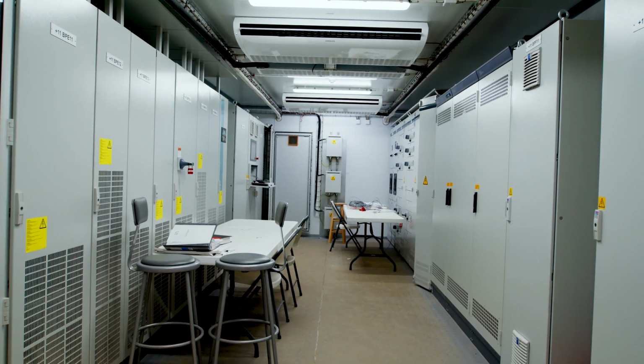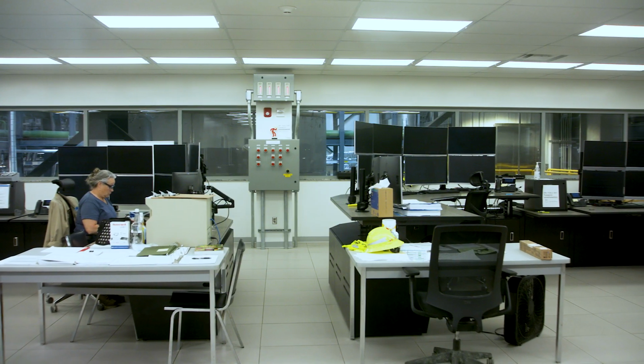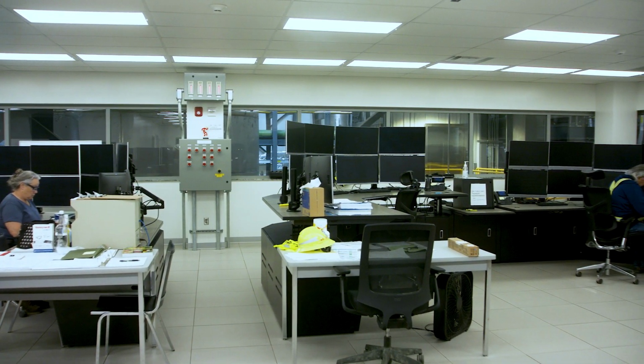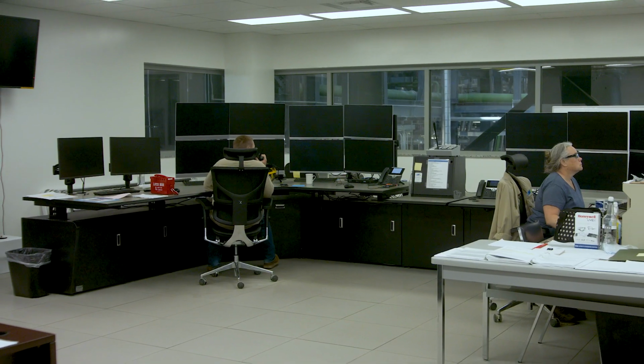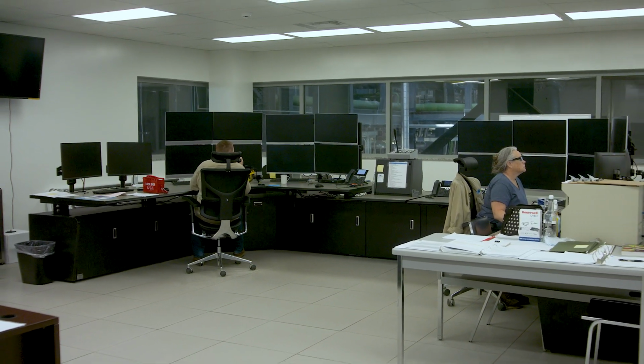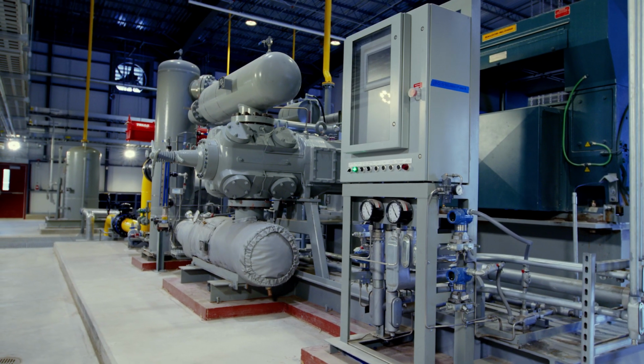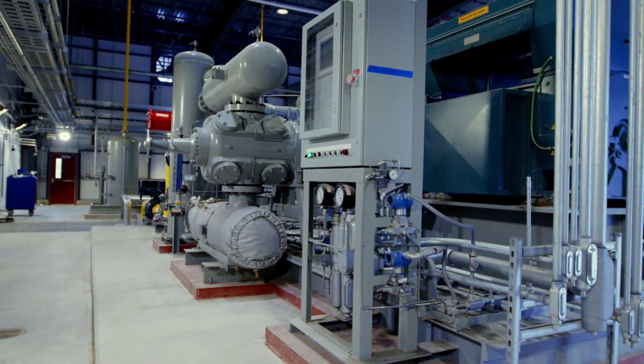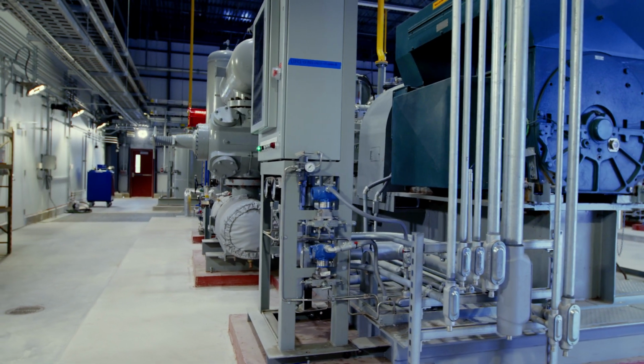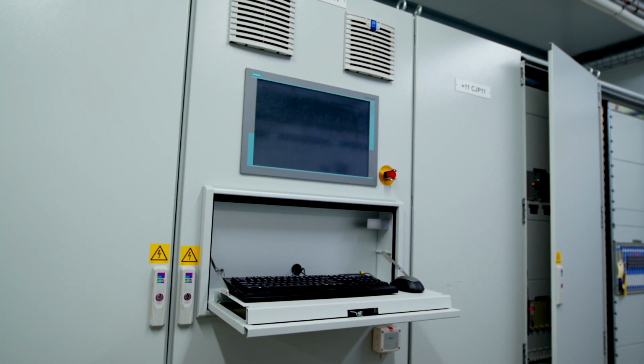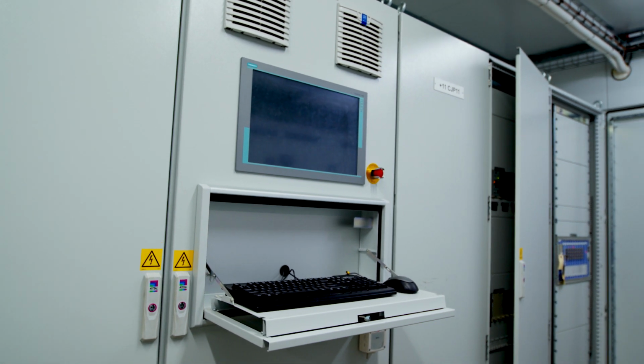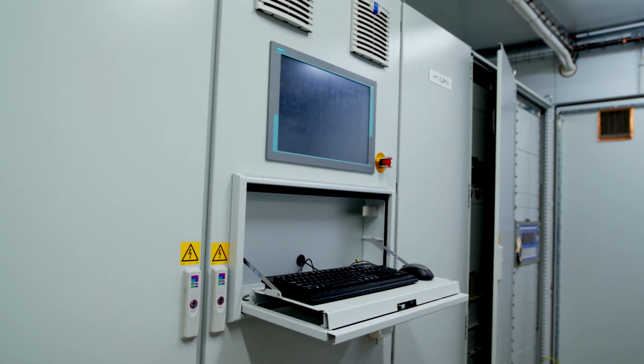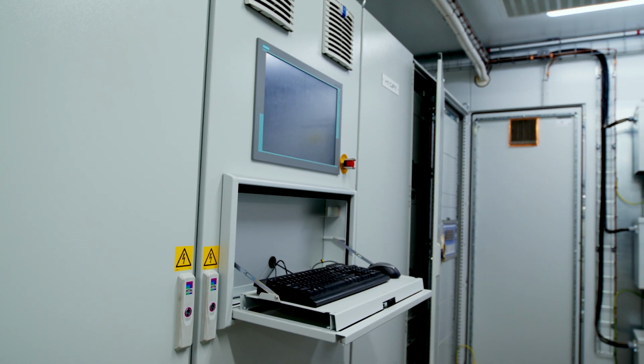All controls at the plant are centralized, safe, and efficient. Everything in the plant can be operated remotely from the control room, with the exception of gas compressors. Those have to be locally started and stopped for the sake of safe in-person monitoring of those processes. The gas turbines each have an individual control room. They can be started and stopped locally, but this is more for emergency situations.